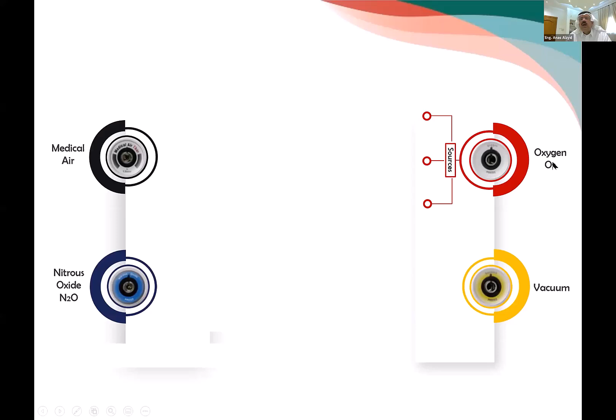For the piped medical gases, there are usually four gases. We have oxygen, and the oxygen either comes from cylinders, from liquid oxygen if it's big, or sometimes from the PSA, which is basically an oxygen concentrator that takes air and concentrates it. They are widely used now. Then there is medical air, again either from cylinders or from compressors. They take the air from the compressor, then you have to have a dryer, and then you supply it to the patient. We need to see that done properly.